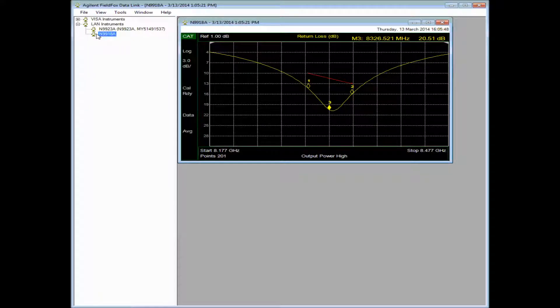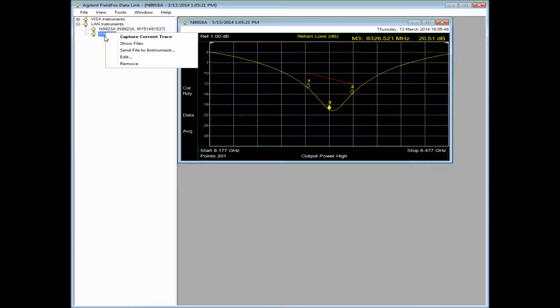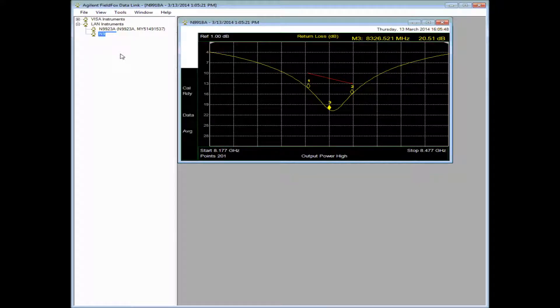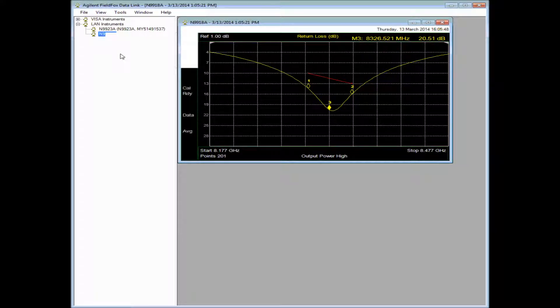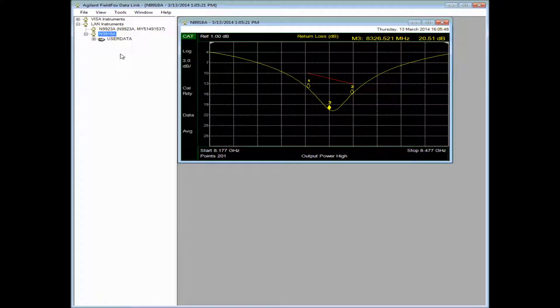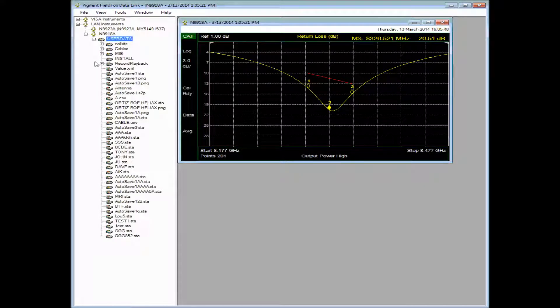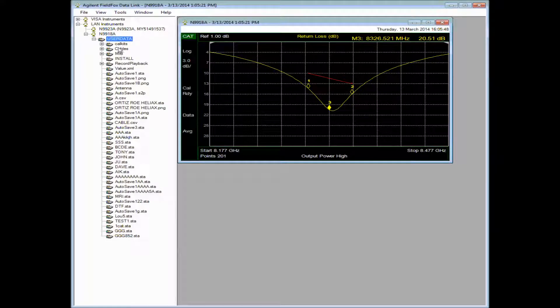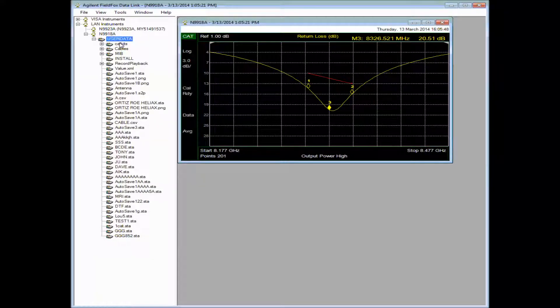If we right-click over the N9918A, we can say Show Files. And what this is doing is going into the memory of the instrument and looking at what files are there. I may have saved states, traces plus state, picture files and that sort of thing. So we can adjust, we can clean up, we can move around files.